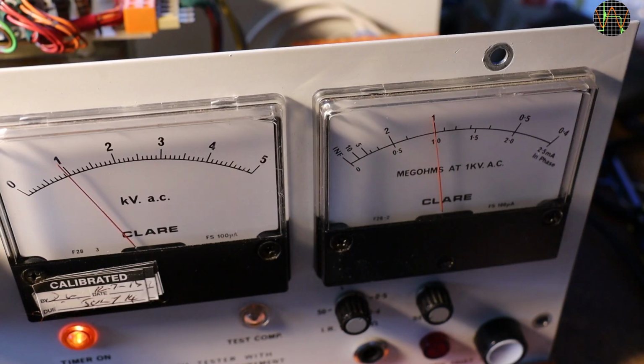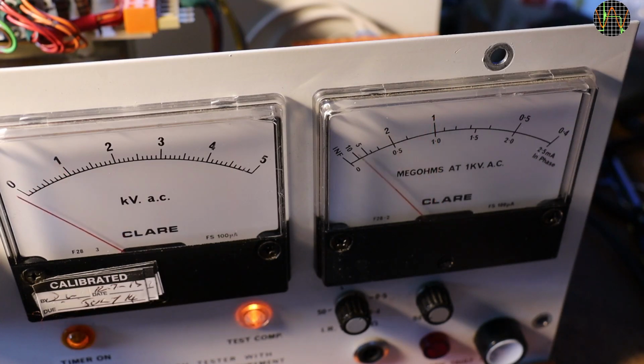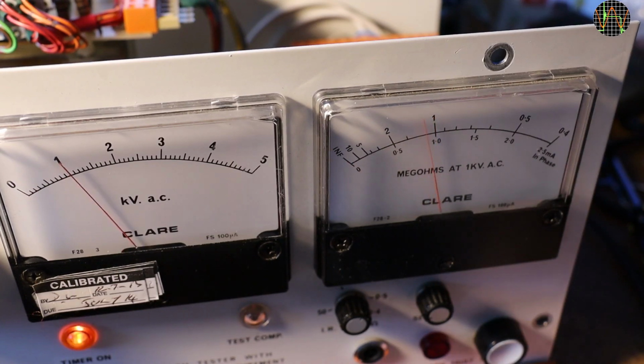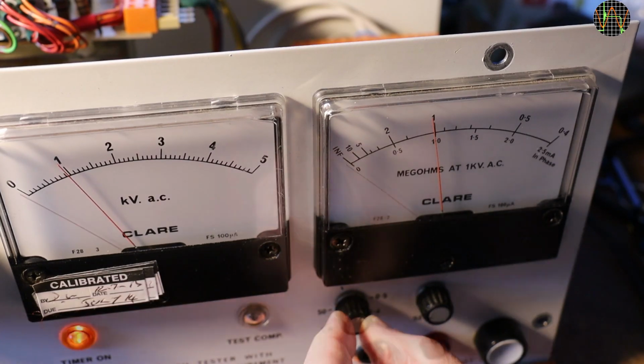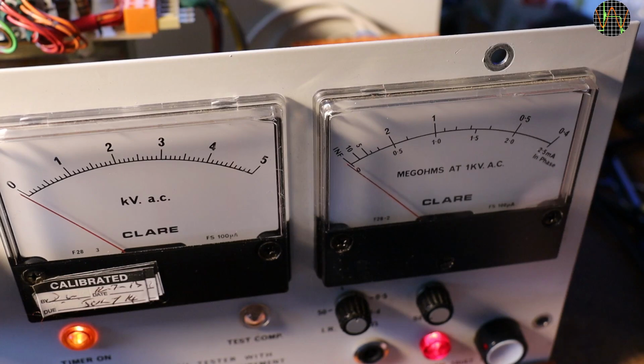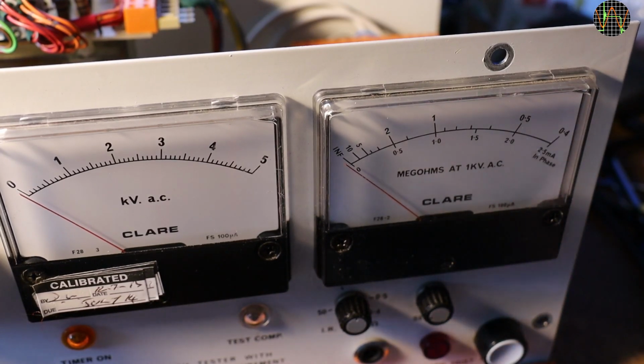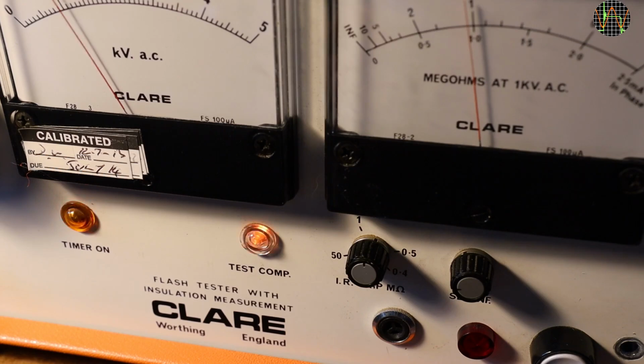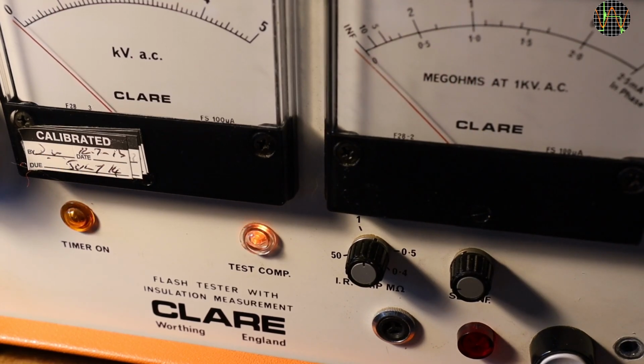Back to the 1 meg test resistor and 1 kilovolt voltage. It measures fine, as you can see, but what I want to know is if the trip still works. For this, I run the test repeatedly, and before every test I nudge the trip setting a little closer to the 1 mark. Finally it trips. The dot on the trip dial is very close to the 1. The few markings on this dial show this is a very non-linear setting, so it can't be more than a ballpark value. For exact trip values, one would need to use the method I just showed, using a known resistor to produce the desired current and adjust the trip dial until the unit just trips. Then there is the problem that the high voltage is not stabilized and therefore fluctuates a little bit with mains.